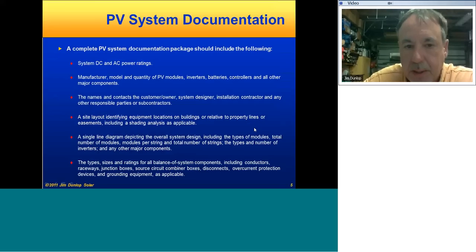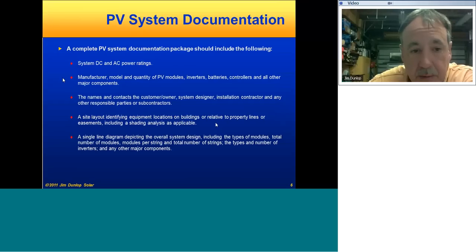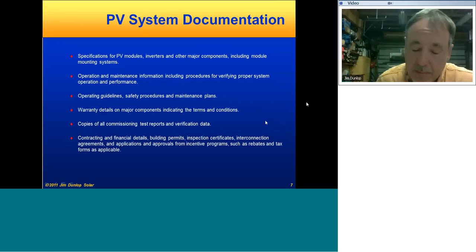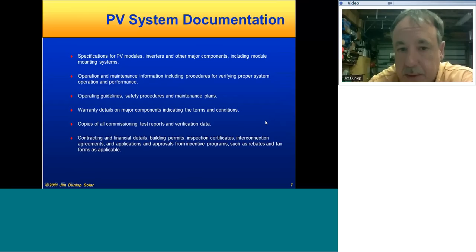So it's very important to have good documentation that includes a lot of stuff, and this is kind of a checklist here. I'm not going to spend a ton of time on this, but obviously some general information about the DC and AC power ratings, manufacturer, model, quantity of major components, contact information for everyone involved in the project or responsible parties, site layouts, single line diagrams, annotations with all the types and sizes of ratings for all the balance of system components, all your conductors, raceways, overcurrent protection, and disconnect means, everything in the system needs to be specified on that diagram. It may be needed in more detailed engineering drawings for commercial projects, obviously, but also other things: all the specification sheets and manuals available for the modules, inverters, other major components, and mounting structures.